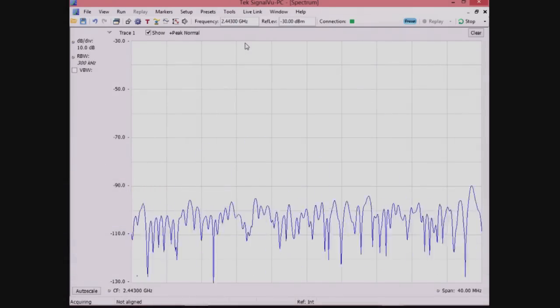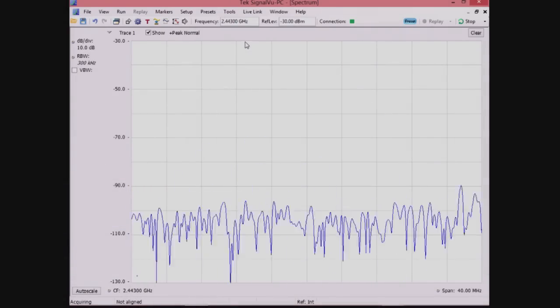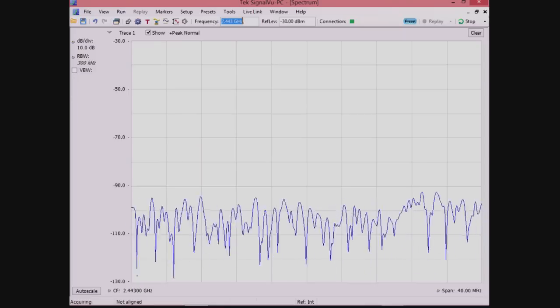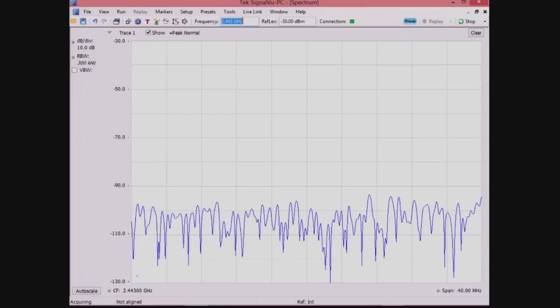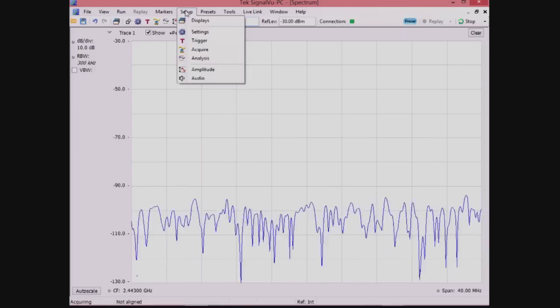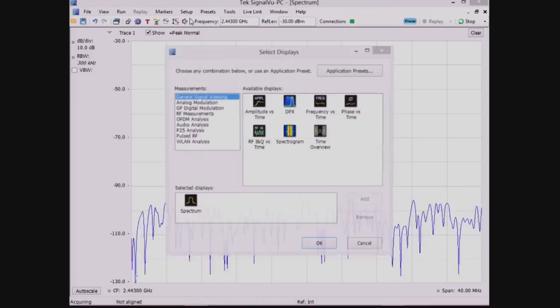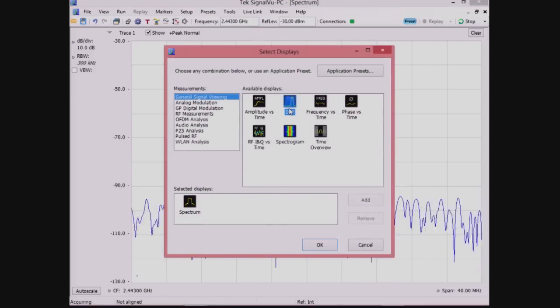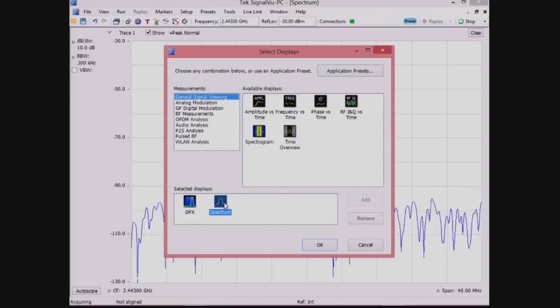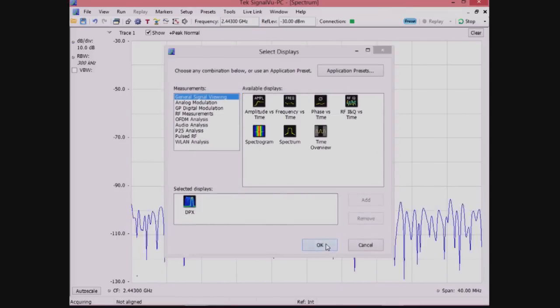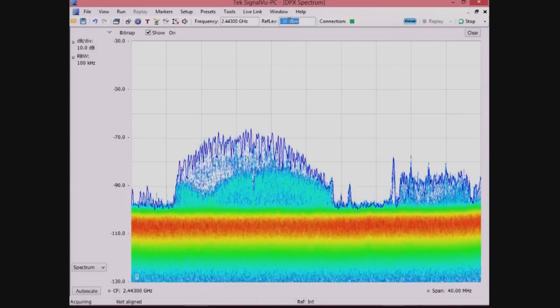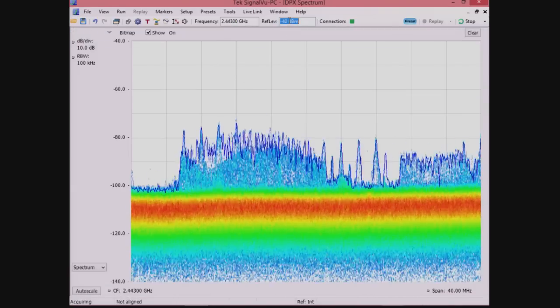We start with the instrument in a preset condition, then tune to the frequency band of 2.45 GHz. Then, we turn on the real-time DPX display. Next, we reduce the reference level to make sure that we can see the signal on the screen.